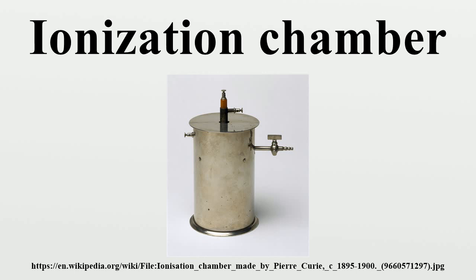There are two basic configurations: the integral unit with the chamber and electronics in the same case, and the two-piece instrument which has a separate ion chamber probe attached to the electronics module by a flexible cable. The chamber of the integral instrument is generally at the front of the case facing downwards, and for beta-gamma instruments there is a window in the bottom of the casing. This usually has a sliding shield which enables discrimination between gamma and beta radiation. The operator closes the shield to exclude beta and can thereby calculate the rate of each radiation type. Some handheld instruments generate audible clicks similar to that produced by a GM counter to assist operators in radiation survey and contamination checks. As the ion chamber works in current mode, not pulse mode, this is synthesized from the radiation rate.